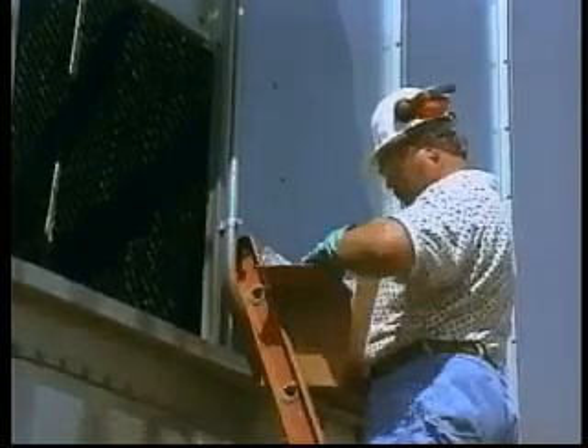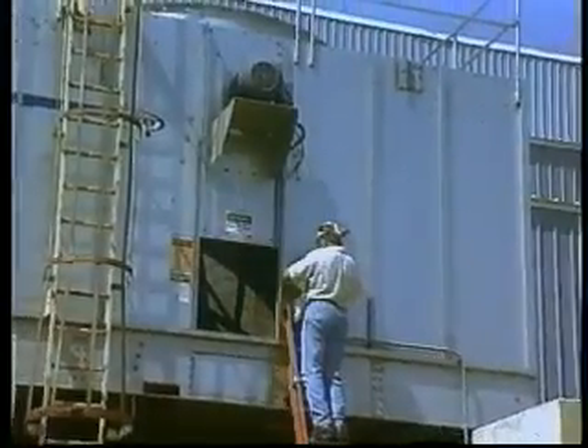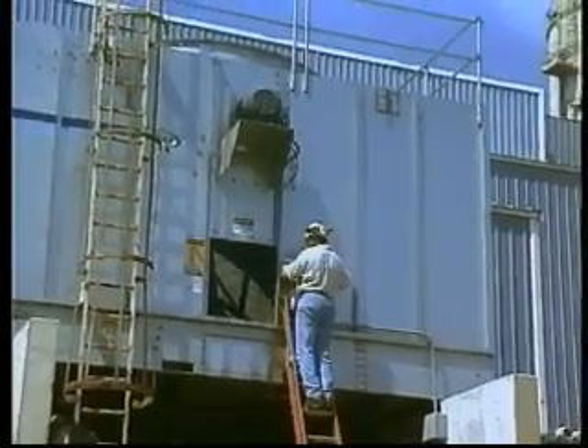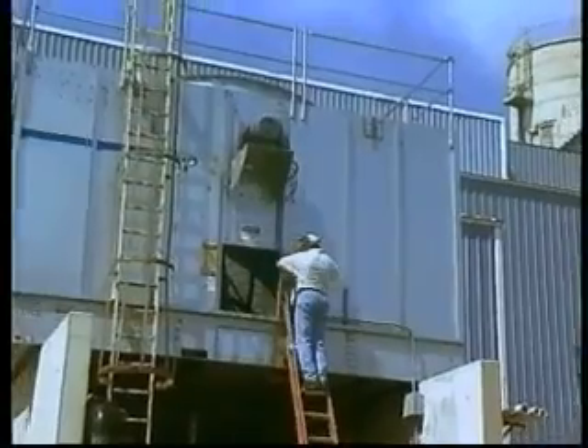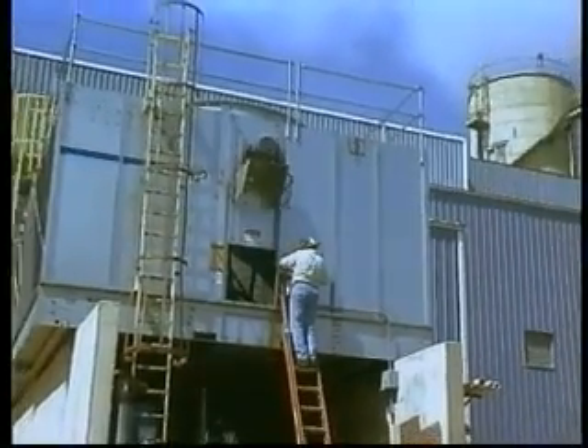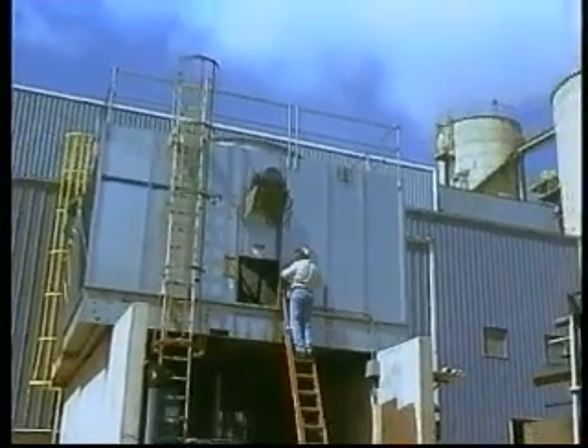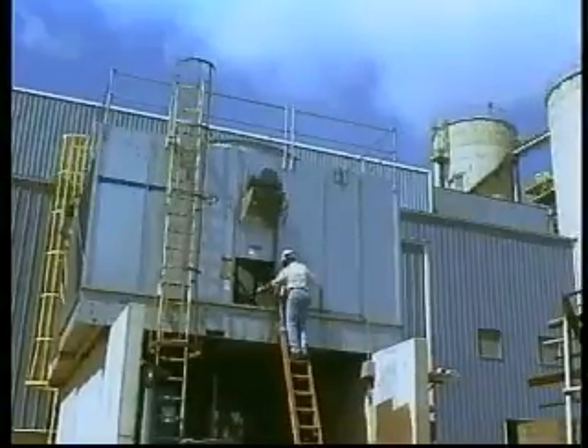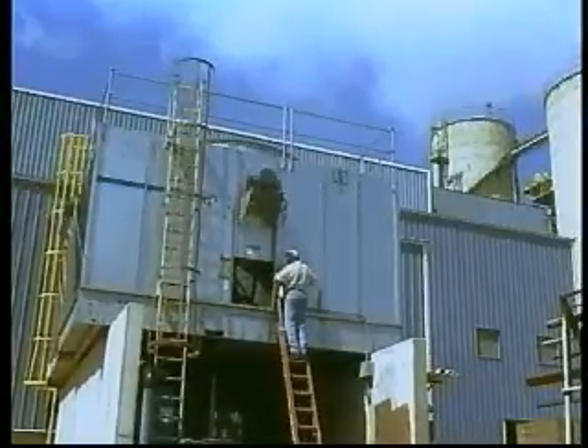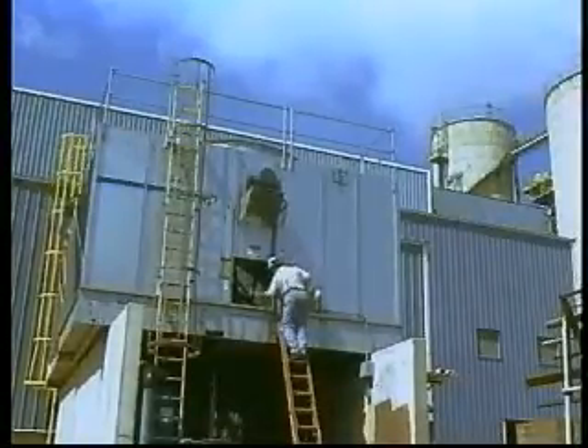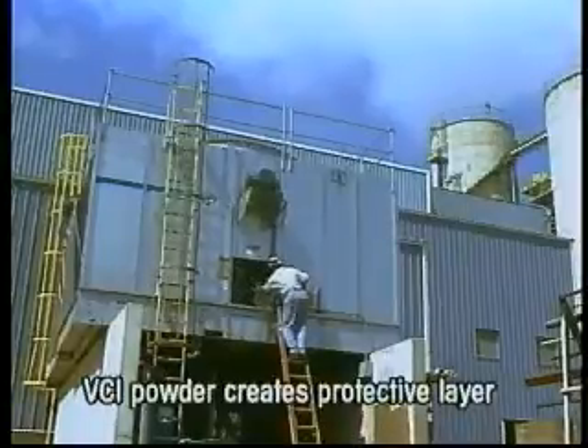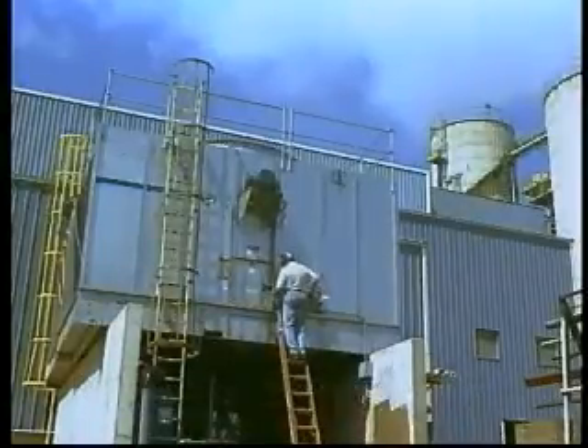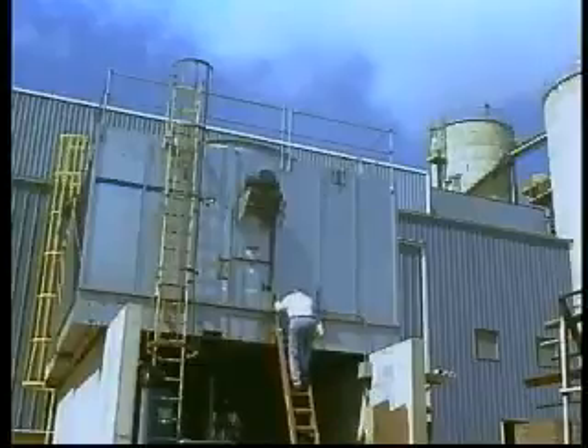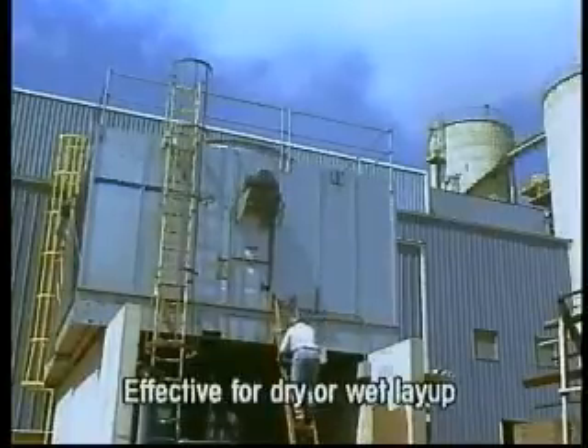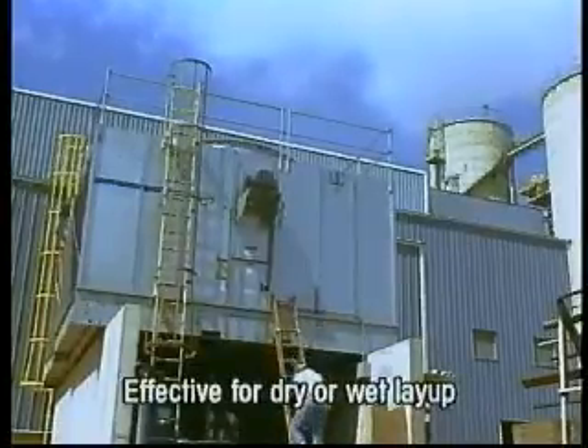The water-soluble bag will dissolve in the cooling water within 15 minutes depending on the water temperature. To obtain a good protective layer, circulate the water through all piping and equipment for at least 6 hours. After 6 hours of circulation, the powder will have reached all of the metal surfaces and created a protective layer. Following the circulation period, the system can be sealed and drained for dry layup or left filled for wet layup.